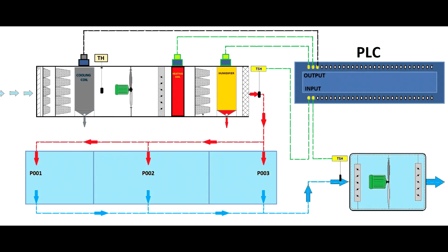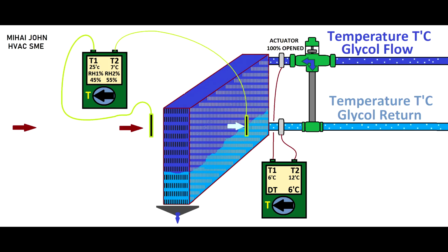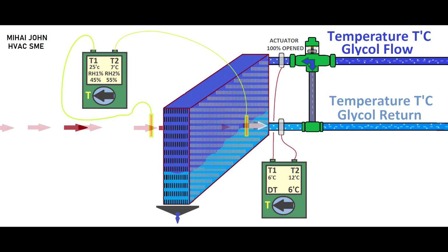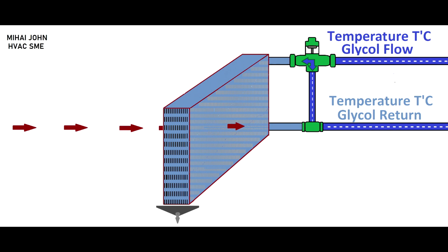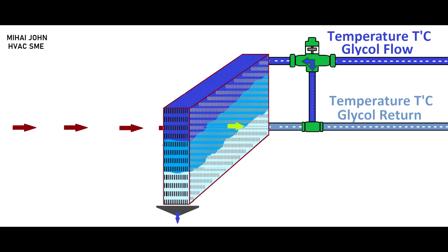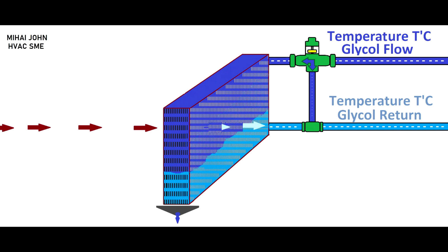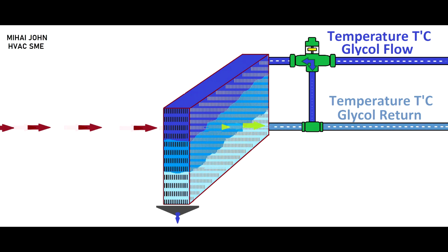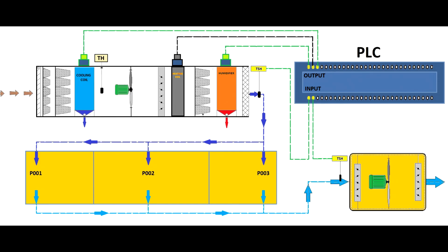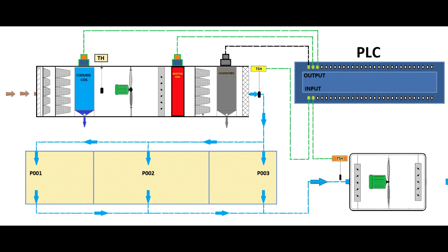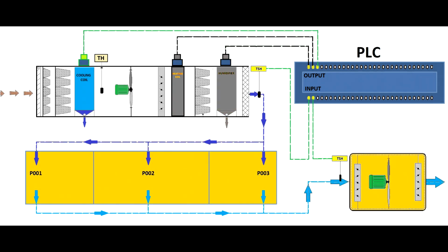Watching this video, it becomes evident that the heat exchanger's capacity is regulated by a combination of factors such as glycol temperature and glycol flow. These factors are managed through valves which are progressively adjusted by actuators following instructions from PLCs, programmable logic controllers. Up to this point, the control mechanism appears sound. However, a critical error lies in the control philosophy's design, specifically concerning the placement of the temperature and humidity probe.